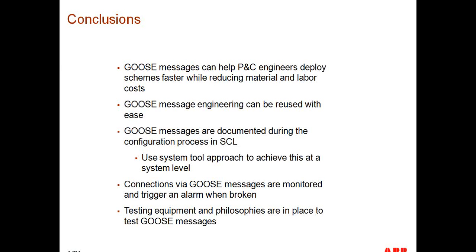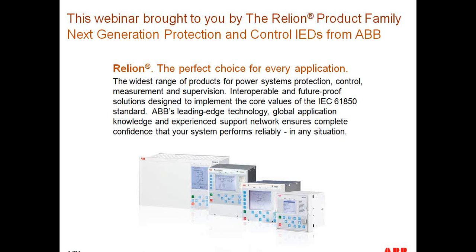Connections via Goose messages are monitored and trigger an alarm when broken. Testing equipment and philosophies are in place to test Goose messages, and this can obviously be adapted and developed based on the particular requirements of the system operator. And with that, I'm going to go ahead and address a few questions that I have here.